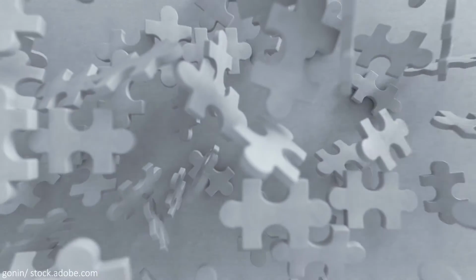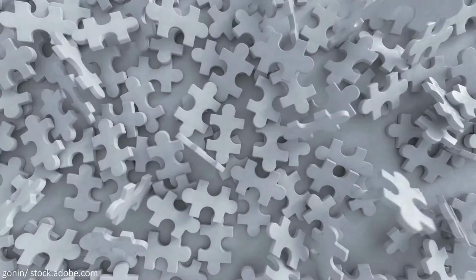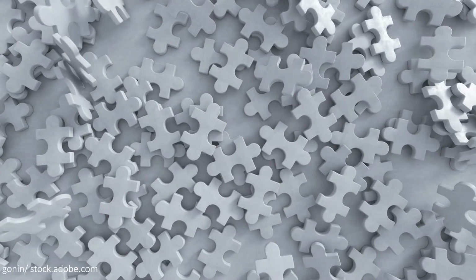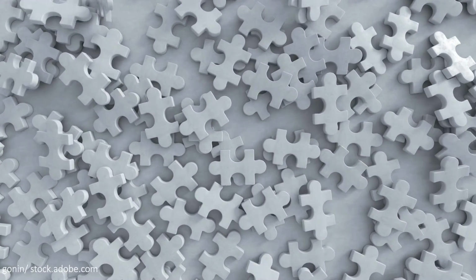So there's a big picture, a puzzle, when a system doesn't work. The big pieces, the easy ones to put together or discount, would be alkalinity, oxygen, pH. Those give you the biggest hints. But then you really have to get down into the weeds. If you've checked all those things and everything looks normal, now's the time to really start some further investigations.